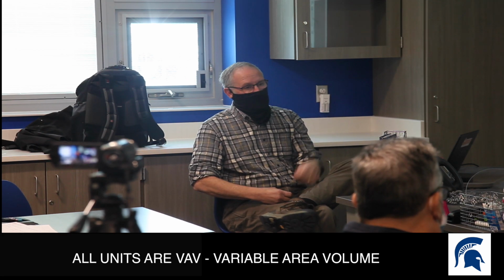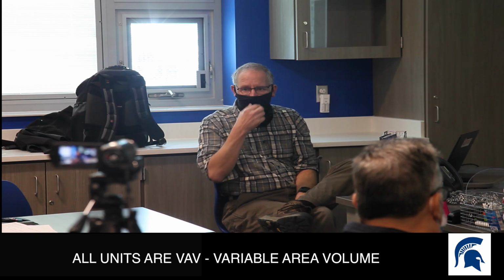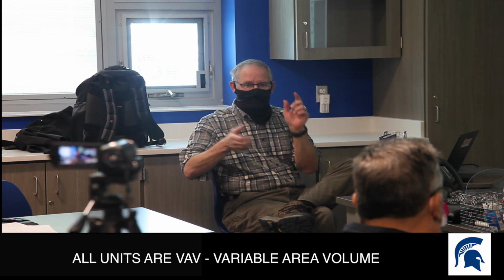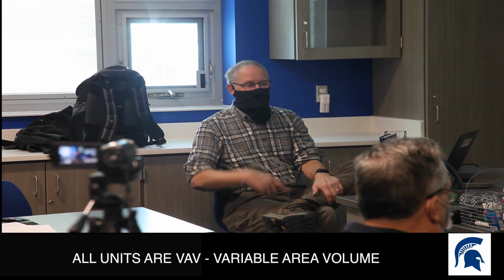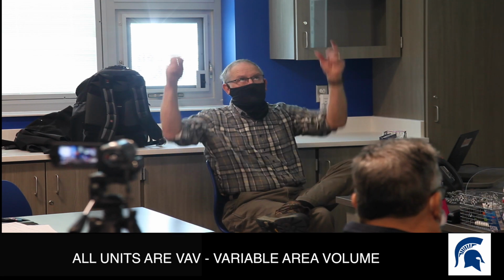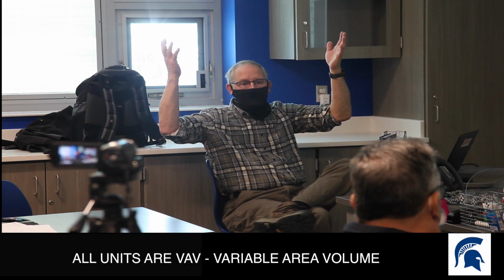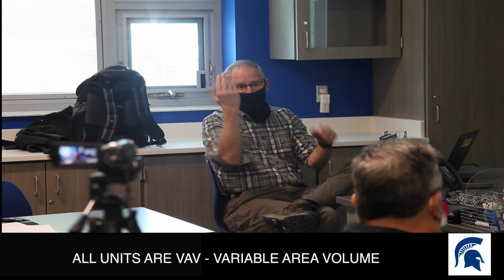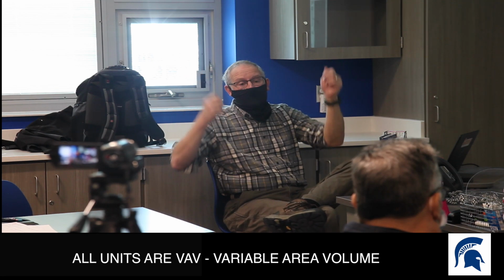It looks like you've got, I don't know what the MERV number is on the filters, but they're all probably the Z-style filters. And when we get up there, we'll yank some, and basically I hold them up to light. Sometimes they look really dirty, but because they load up very evenly, if you can see light through them, they're still okay.